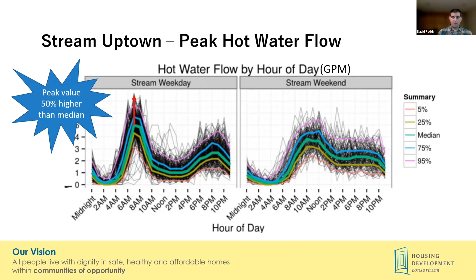One thing to see is that at the peak, the flow is oftentimes 50% higher than the average. And for sizing systems, we always have to look at the peak. So if you have average data, you should think about multiplying that by 1.5 to understand what your real peak is. And it just so happens that this profile is very similar to the one that the EcoSizer, the tool used for sizing heat pump systems, uses. It's something to understand when looking at load shifting or sizing storage volume. This is the design day profile that's built in, and so that can have an influence on sizing systems.